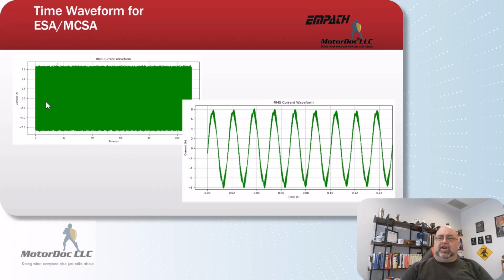Now let's get into, for those who are into vibration, time waveform. For us it's kind of like this. So it'll be this or the RMS value. We'll take this as my peak to peak. So this is basically from 0 to almost 8 amps each direction. If I bring it down, it is 8 amps. This is the waveform itself, and you'll notice that I have noise on top and identical noise on the bottom. This, by the way, because here's my 0, is why we have sidebands instead of the exact value, because we see it on the upside and we see it on the downside. It's an amplitude modulated signal. I'm not going to throw the math in here for that, but know that it's plus or minus the carrier frequency, and this is my carrier frequency.